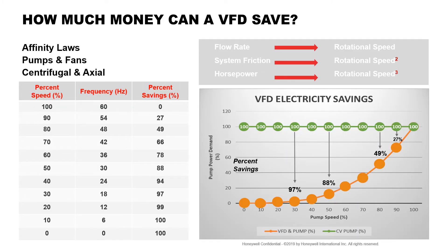We can calculate the energy saved when a VFD reduces the speed of a motor based on the affinity laws, also known as fan laws or pump laws. These laws apply both to centrifugal and axial fans and pumps. When a motor is running at full speed, or 60 Hz, there's no energy saving. But if we reduce the speed by just 10% to 54 Hz, it will reduce the energy used by 27%. If we reduce the speed of the motor by 20% to 48 Hz, it will reduce the energy used by 49% — almost half the energy used by reducing the motor speed by just 20%. That's a significant energy savings for the end user.